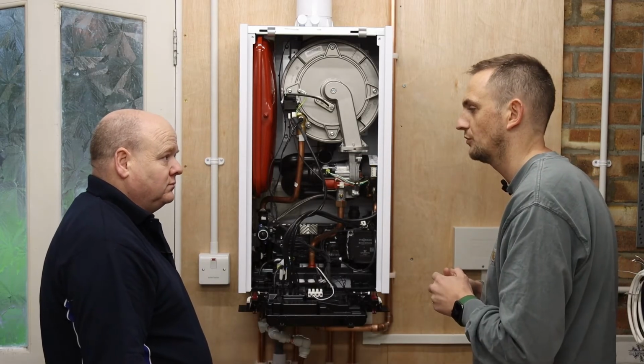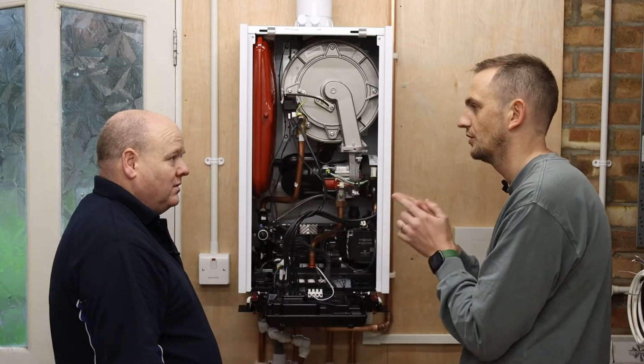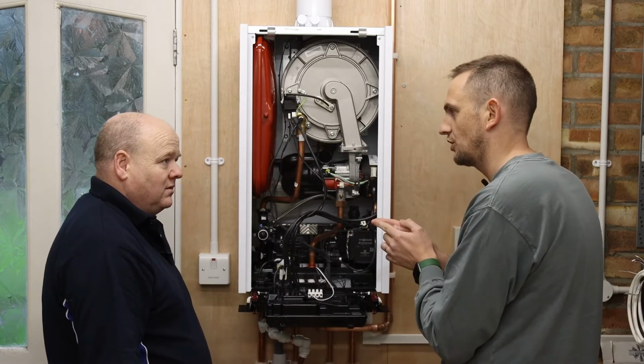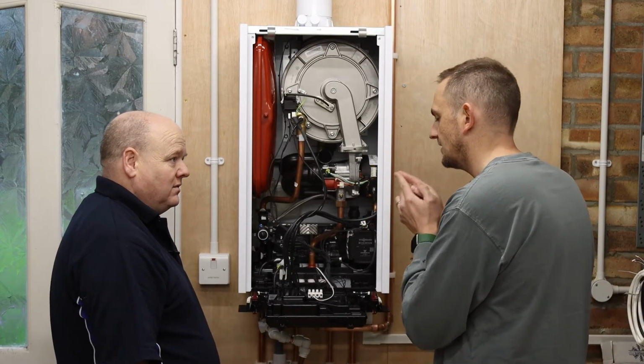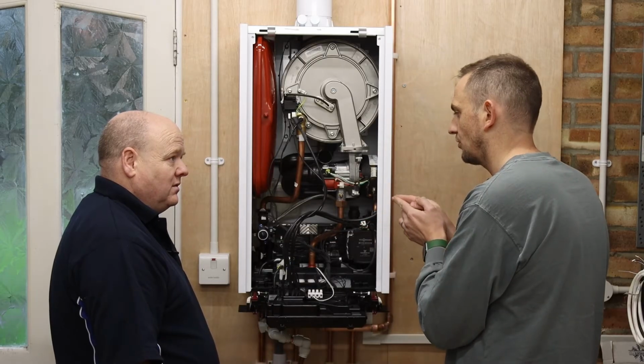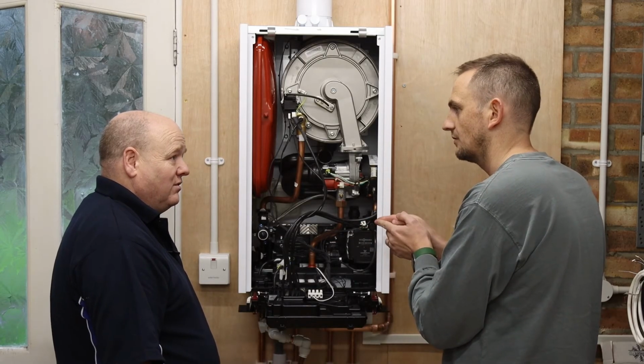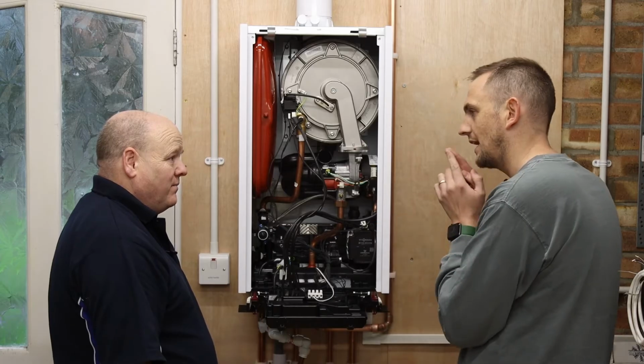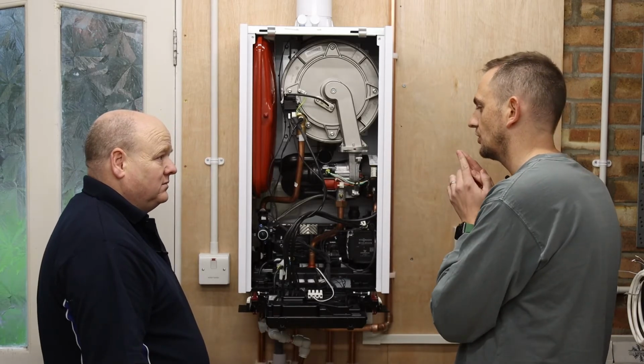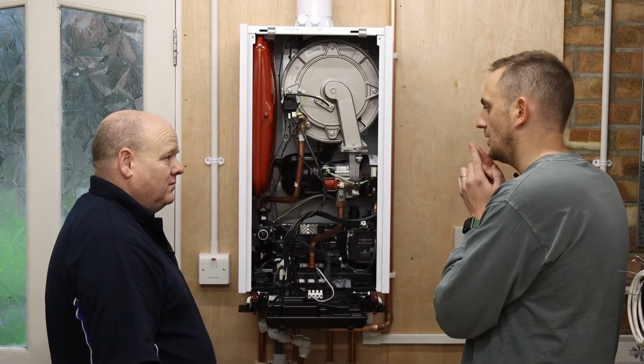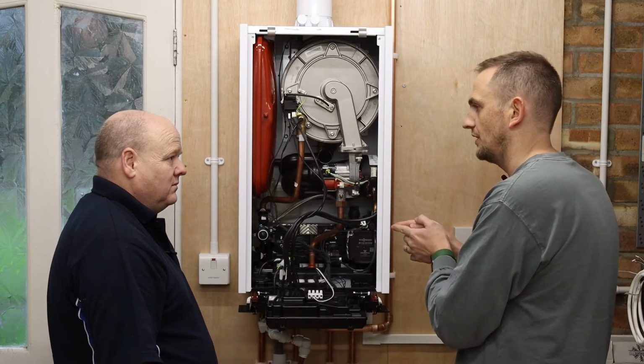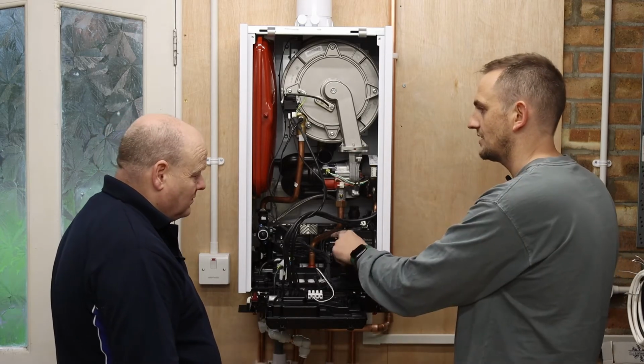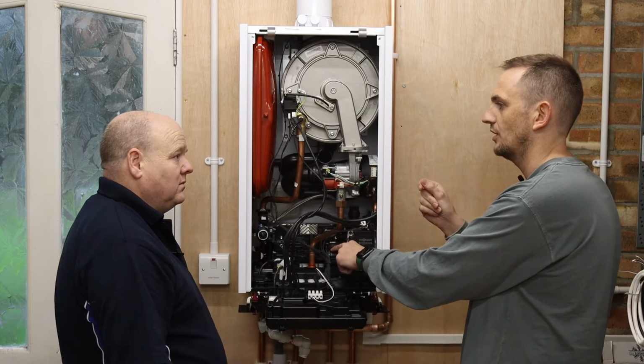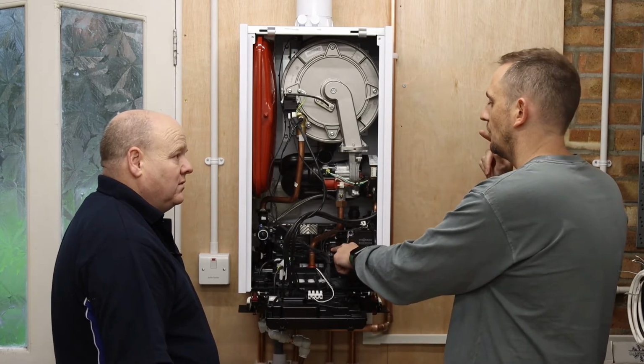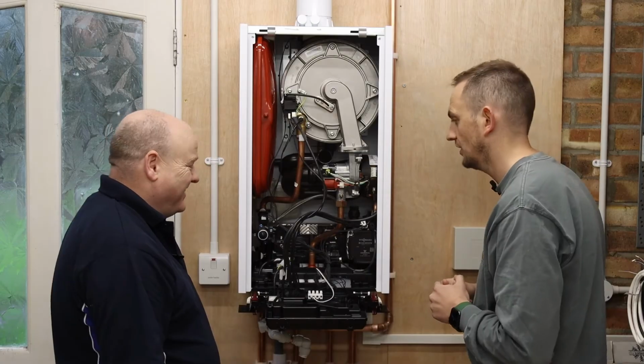You mentioned the shock arrestor before. Right, I've remembered - the reason it doesn't need a shock arrestor is because that's rated to something like 300 PSI. So that's why it hasn't got one, because you can fit a non-return valve on these, since that transducer is quite sensitive to firing the boiler if you get a bit of backflow. I just remembered that now. That's brilliant, that's funny. Right, there we go.